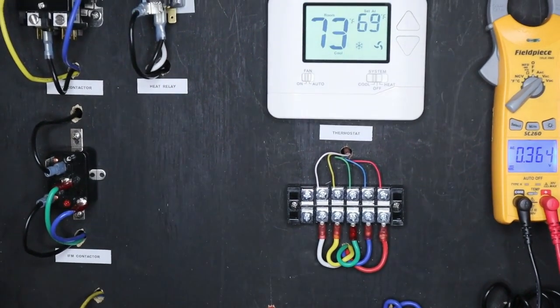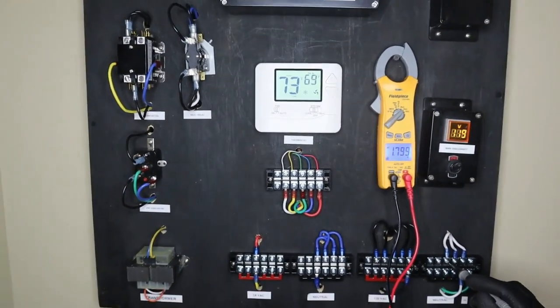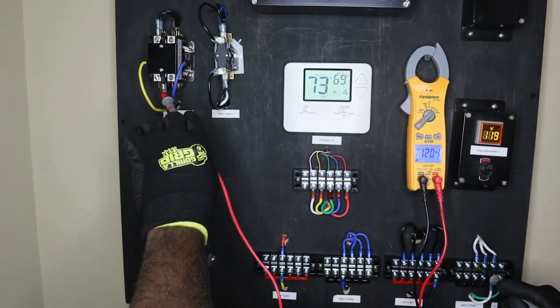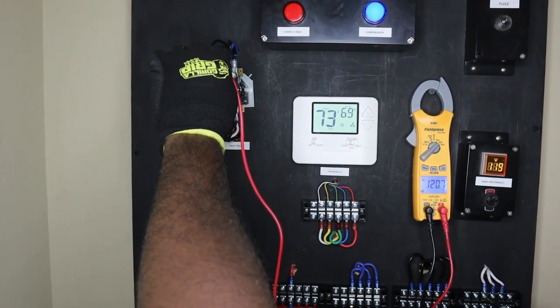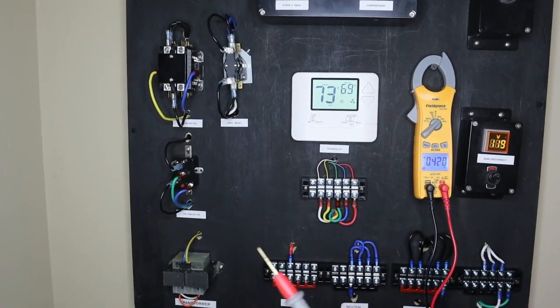Now let's measure the input to our contactor. So we place one of our terminal blocks on neutral, we see we have 120 volts. We have 120 volts going to our contactor and at the output we have 120 volts. So we know our contactor is pulled in.